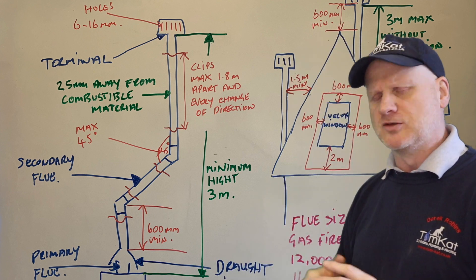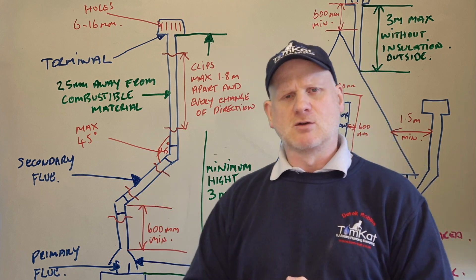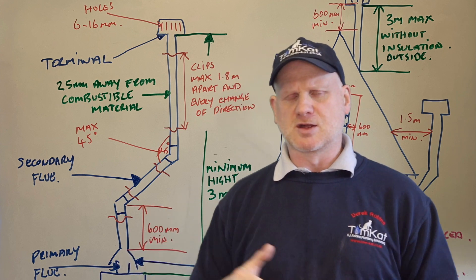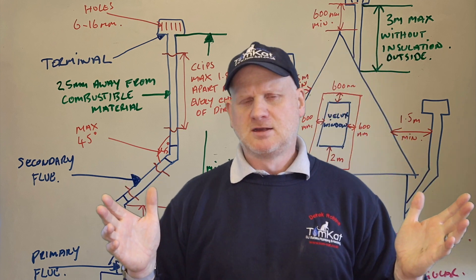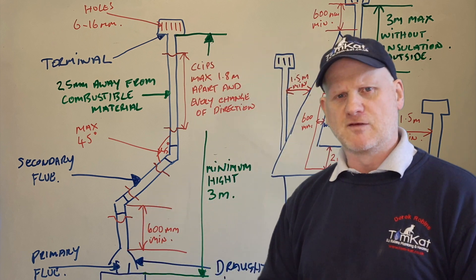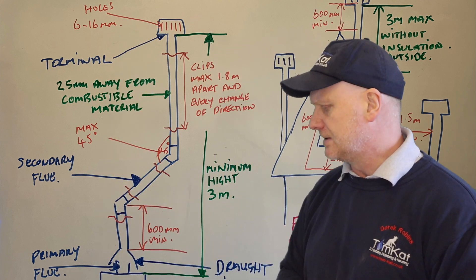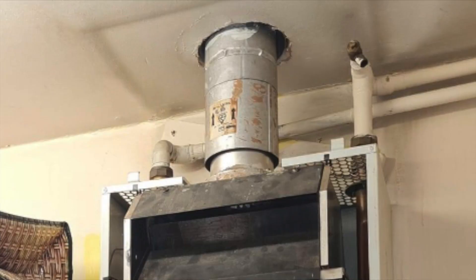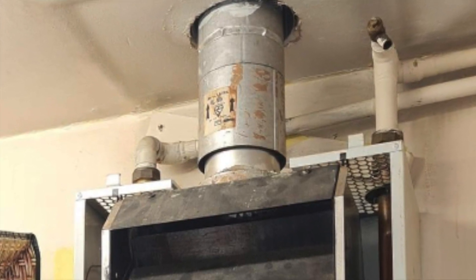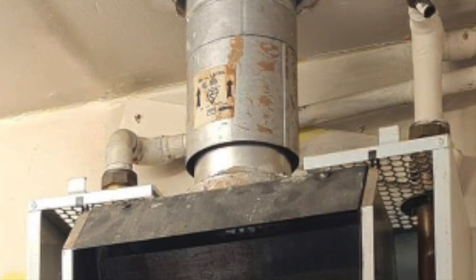If you come across boilers with horizontal parts or less than 600mm to the first bend, they're at risk. The secondary flue must be twin wall — you can't use flue liner connecting to an open flue boiler unless it's a back boiler in a builder's opening. In the loft it must also be twin wall, not flue liner or single wall. When connecting twin wall to the appliance, you must use an appliance adapter, sealing only the inner flue to the appliance.